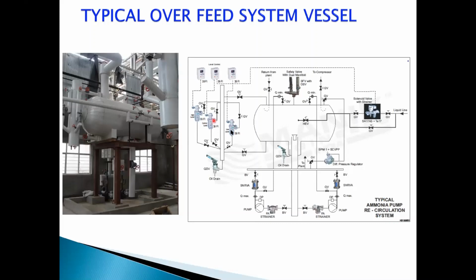Why do we need these three? These are centrifugal pumps, and to operate these pumps, you need to maintain NPSH, or net positive suction head. Liquid has to be there in the ammonia pump. The pump has to always be filled with liquid to operate. So this low level maintains a constant level in the vessel such that this NPSH to the pump is maintained. In case the level tries to go below the low level, then it can switch off the pump and protect the pump. Then we have a differential pressure switch across the pump, so that if the pump pressure tries to go very low, it can trip the pump.